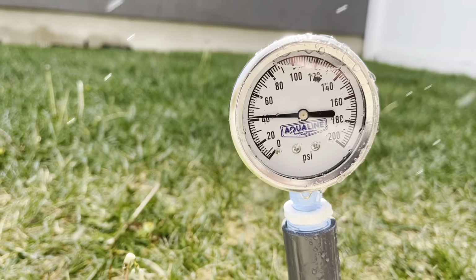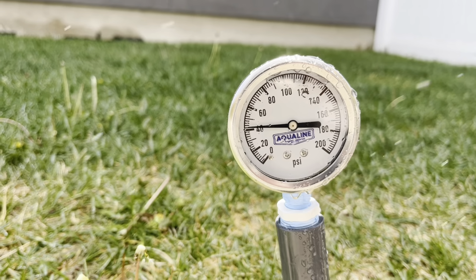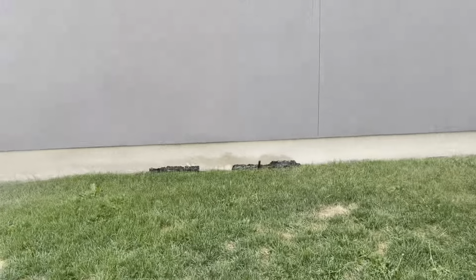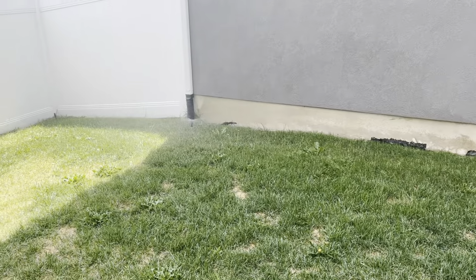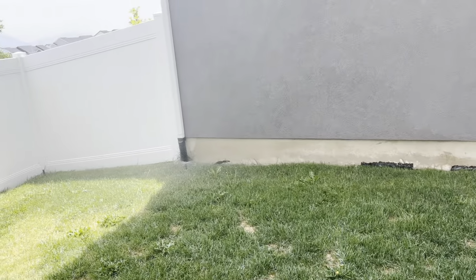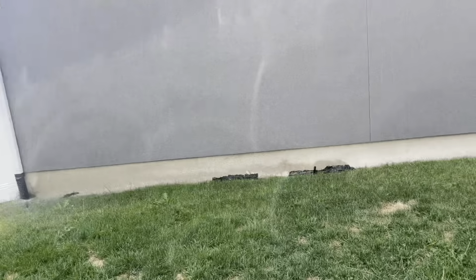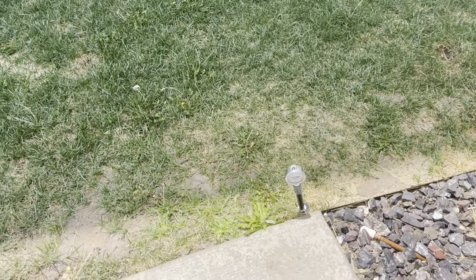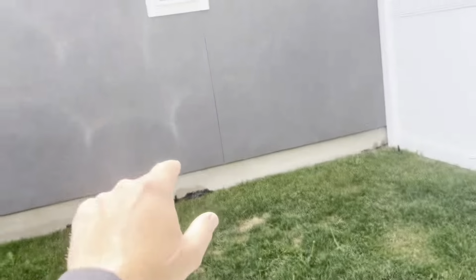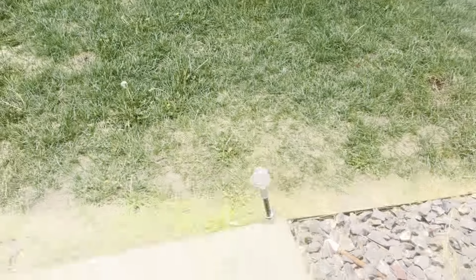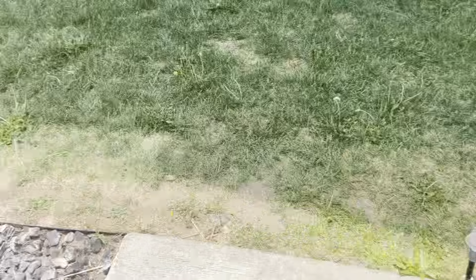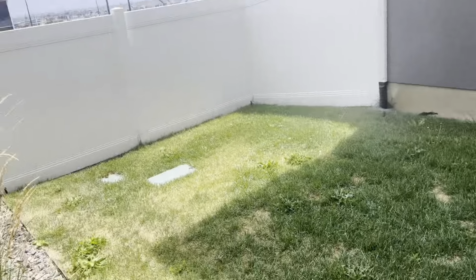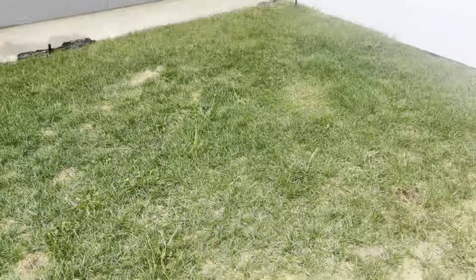Now we're down to almost 40. So we're losing like 18 PSI per head, which is just crazy. So we've got some issues here that we need to work around, right? If we're losing like 20 PSI per head that we open, then really we're gonna be able to open 1, 2 more, and this is gonna be down close to 0. And then these aren't gonna be able to open at all because we're not gonna have enough dynamic pressure.